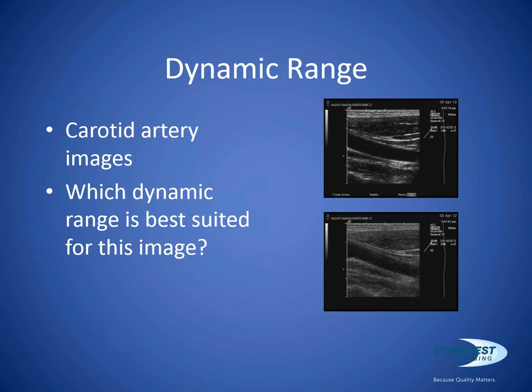Frame rate. Frame rate is something that the system will vary depending on whether you're using multiple focal zones. A lot of systems will allow you to change the image width in order to increase frame rates. If we're doing, say, an echo study, especially on a child, their heart rates are much higher, and so you need very high frame rates for the system to keep up with the motion of the heart. By using multiple focal zones, we're decreasing frame rate. Some systems will allow us to adjust. There'll be a setting called image width that will allow you to narrow the width of the image in order to bring your frame rate up.